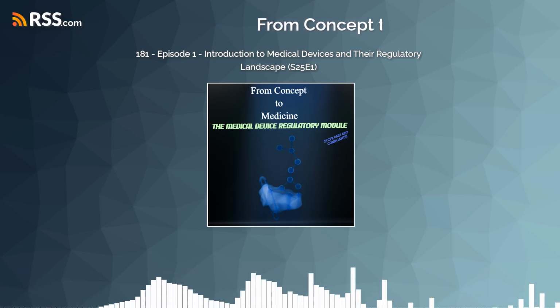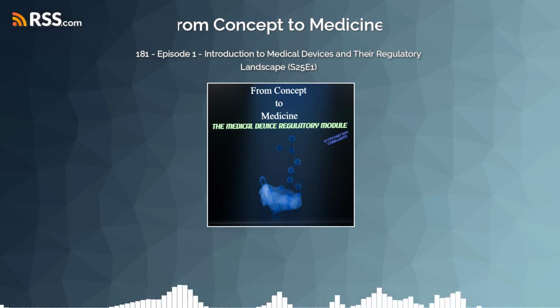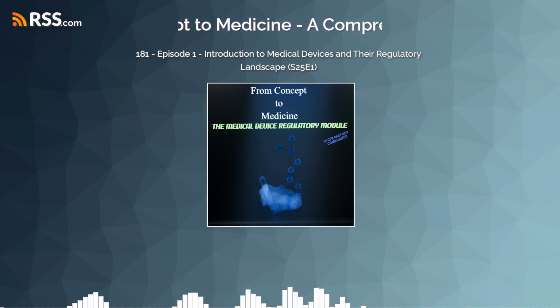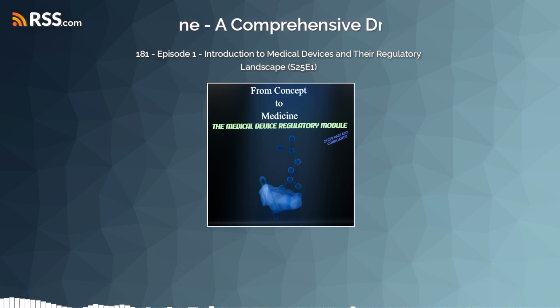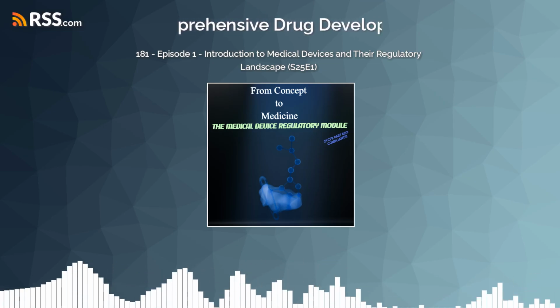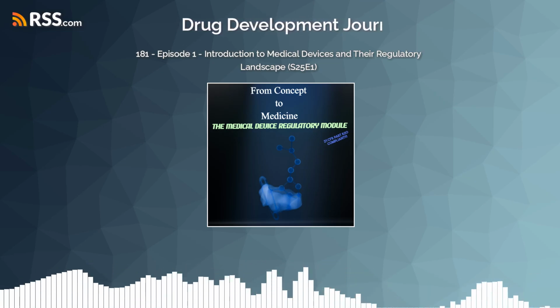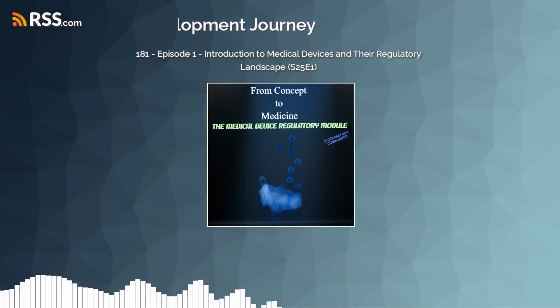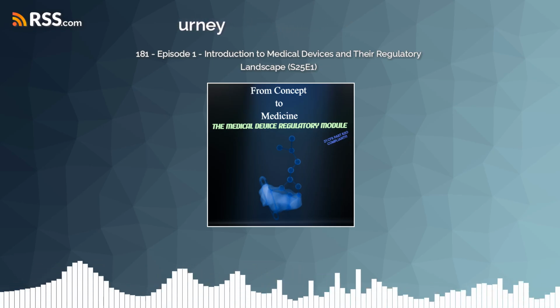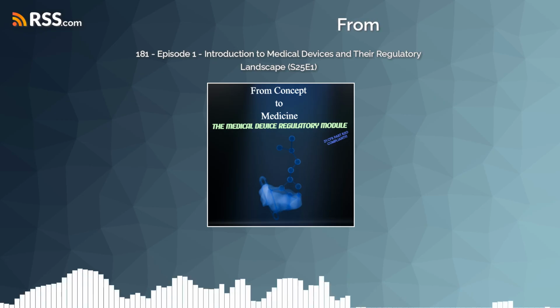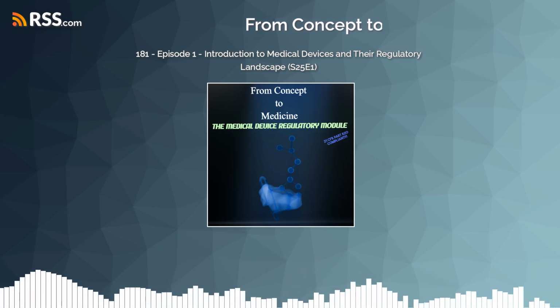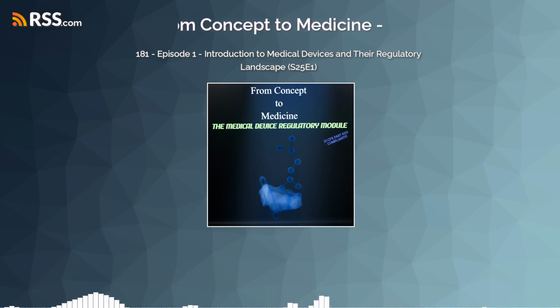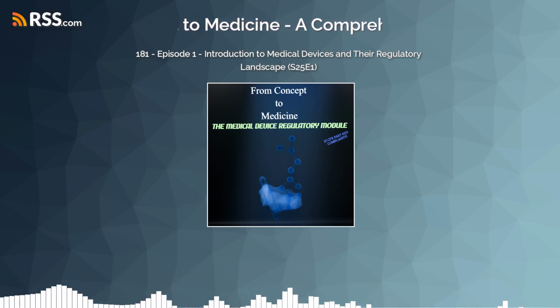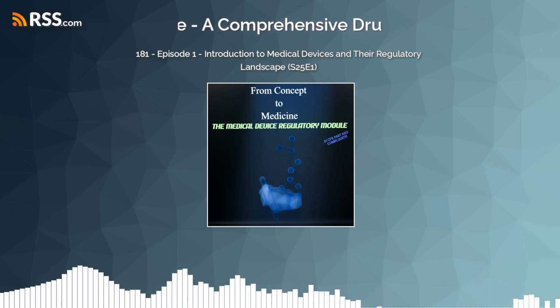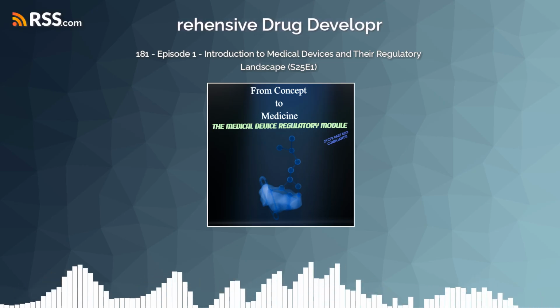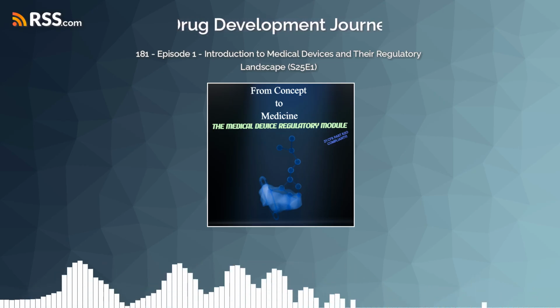Exactly. And it sounds like risk management is just built into this entire process from day one. How deeply integrated is it? Oh, it's absolutely foundational. The FDA expects risk management, often guided by international standards like ISO 14971, to be embedded in both the design and the manufacturing stages. It's a systematic approach. You identify hazards, estimate and control the risks, and this ties directly into device validation. It guides decisions on changes or complaints throughout the device's entire life cycle. It's really a continuous loop of ensuring safety.